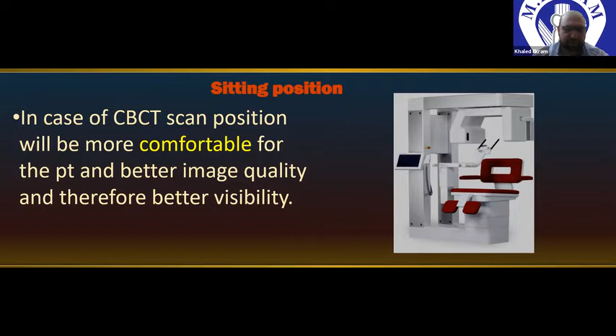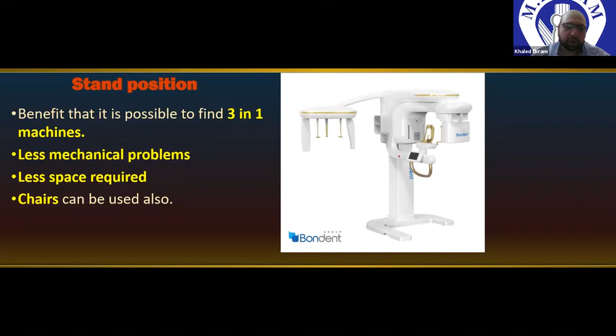But the standing position machines have some more benefits. Number one, there is no chair here, so the boards and the parts of the machine which cause mechanical problems are less in case of standing position machines. Also, it requires less space. Also, this is more suitable for patients in a wheelchair. In addition, in standing position machines, it is possible to place 3 imaging modalities in the same machine. We can place a panoramic sensor, cephalometric, together with the CBCT, what we call 3-in-1. But in case of sitting position machines, it is not possible to put a cephalometric arm. This is not possible. So space saving is very good in this case.